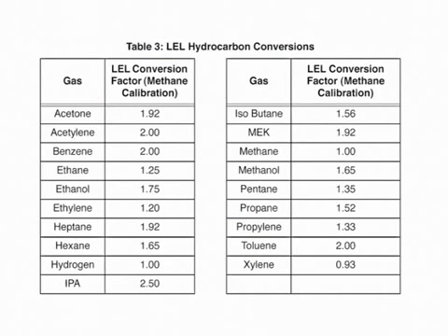Although the standard factory setup and calibration for the combustible gas channel is to methane, CH4, the combustible sensors will respond to other combustible gases as well. The table shown lists the conversion factors for several hydrocarbon gases for the % LEL combustible sensor if it is calibrated to methane. Conversion factors are not available for the % volume TC sensor.